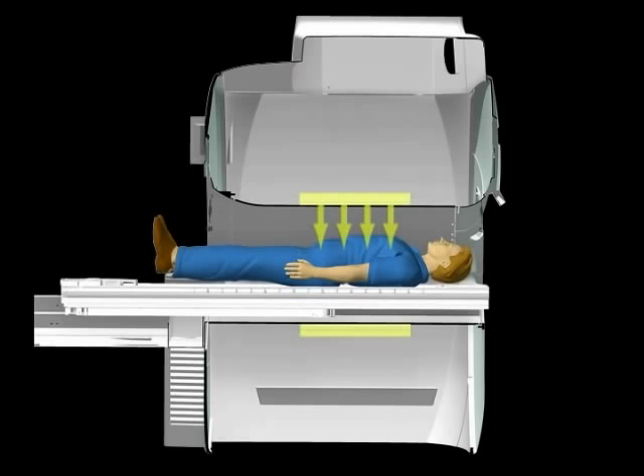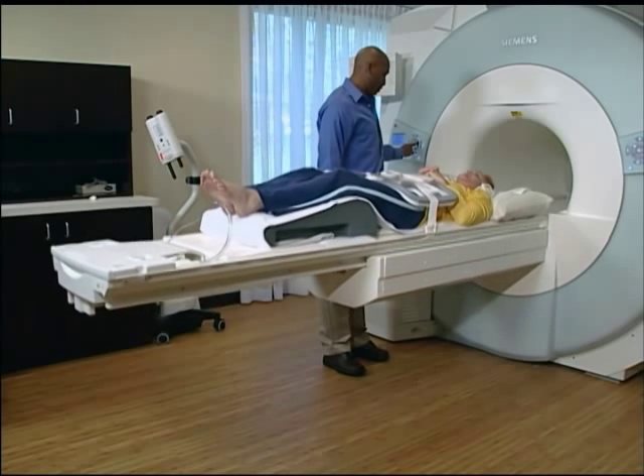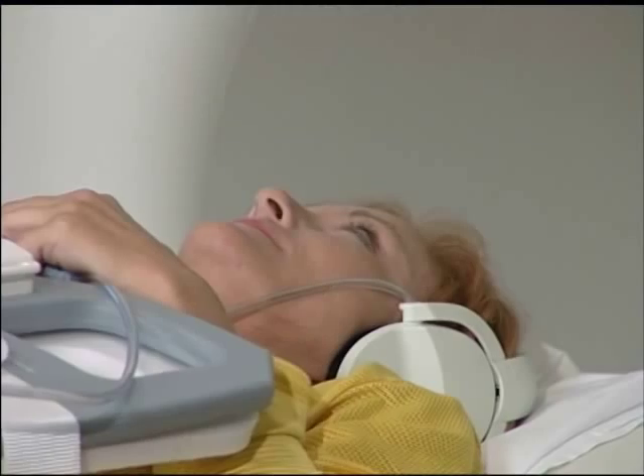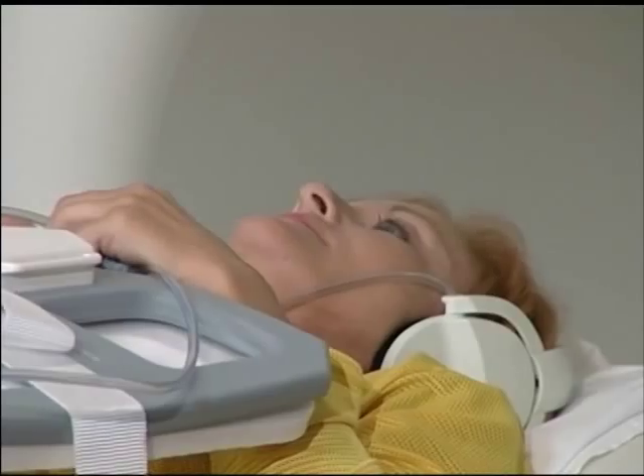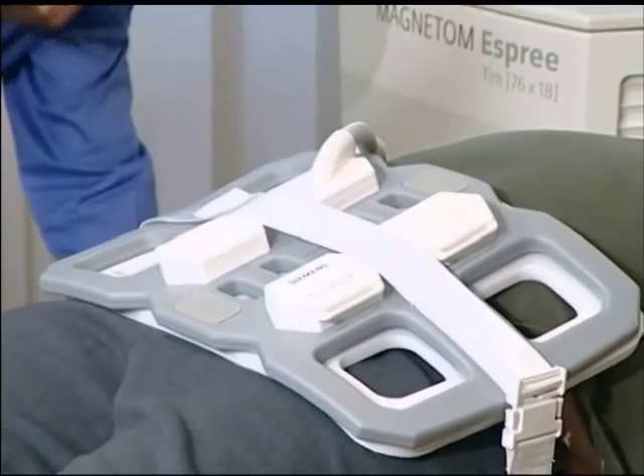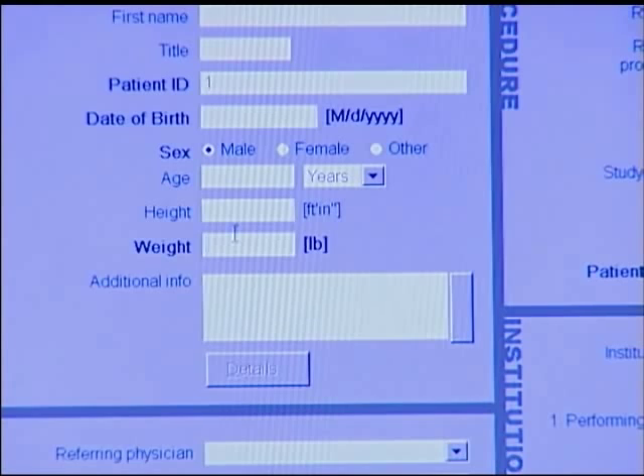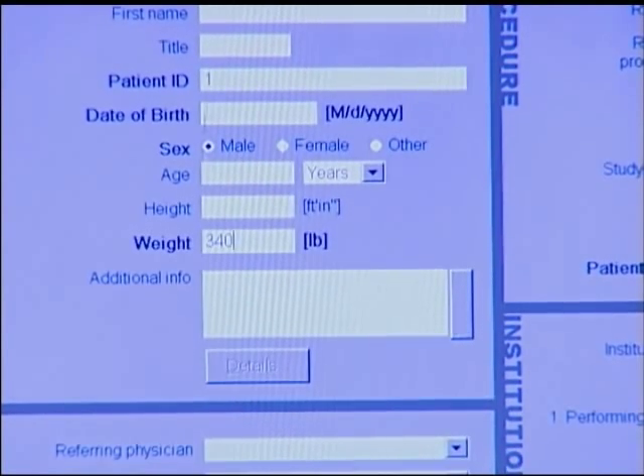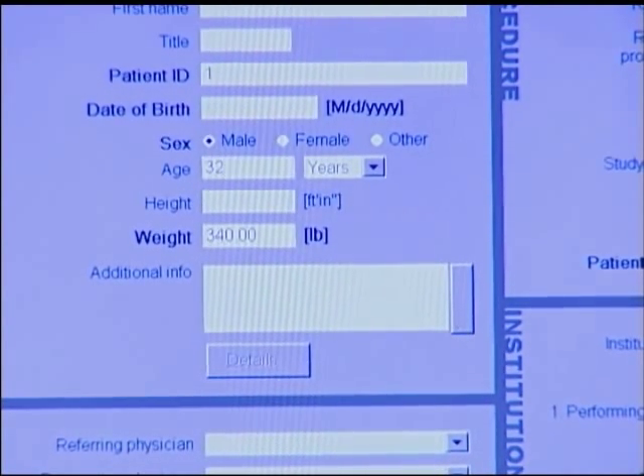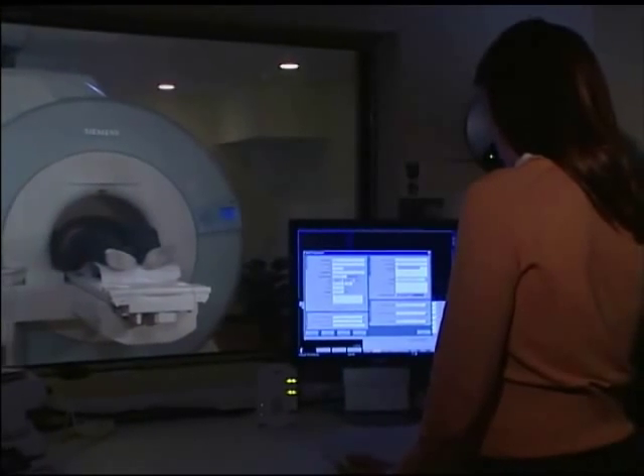However, Siemens MR systems are equipped with safety devices for controlling the switching speed and the strength of the gradients to prevent nerve stimulation. The RF used in magnetic resonance imaging is absorbed by the body and can cause localized warmth. For safety reasons, control circuits in the MR imager prevent the energy absorbed by the body, known as SAR, from exceeding safe thresholds. Since the computation of SAR involves the patient's weight, it is important to enter this information correctly during registration. The limit values are fixed by international safety standards.